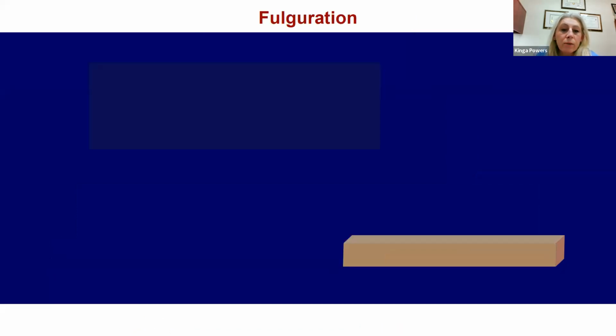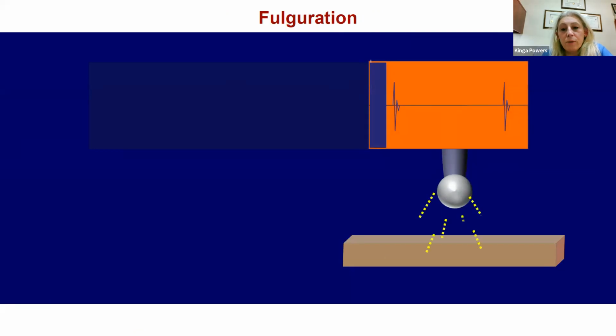Another non-touch mode is fulguration, which is the opposite of the touch technique — it's basically a visible arc between the tissue and the electrode. It's a high voltage mode on the blue coag button, and it can reach over 200 degrees Celsius or more, causing desiccation and breakdown of organic molecules and carbon, giving a dark hue to the coagulated tissues.